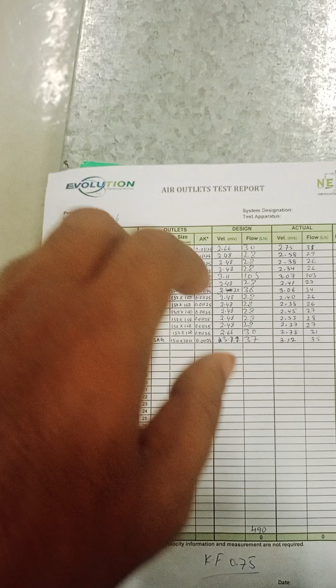Here the unit data will go to the AHU and there is a nameplate. We see the nameplate and note it here. This is supply fan data. Here pressure drop, we will check pressure drop at 4 places: pre-filter, bag filter, cooling coil, heating coil. Here design will be and we note down the actual and write here. Supply fan data, there is a nameplate. We take the nameplate picture and design will be here in the nameplate and we measure the actual and write it here. Return fan data, we take the nameplate picture, design we write here and actual we note and write here.